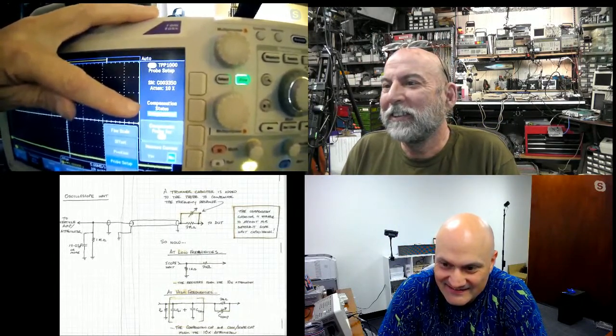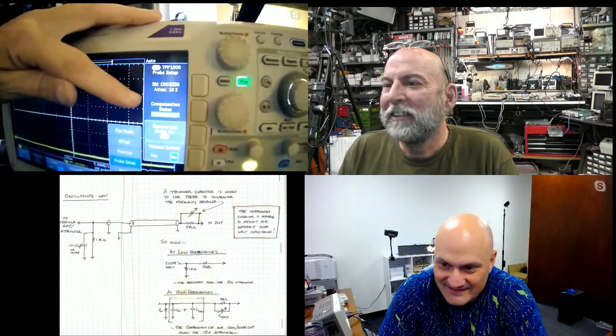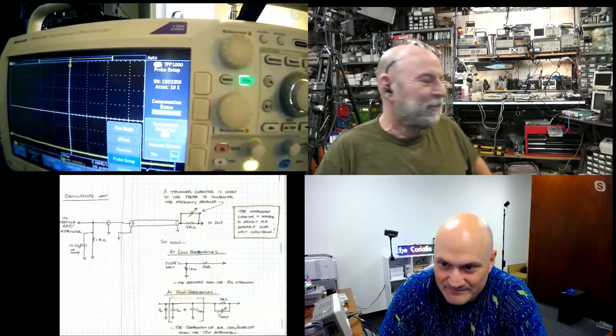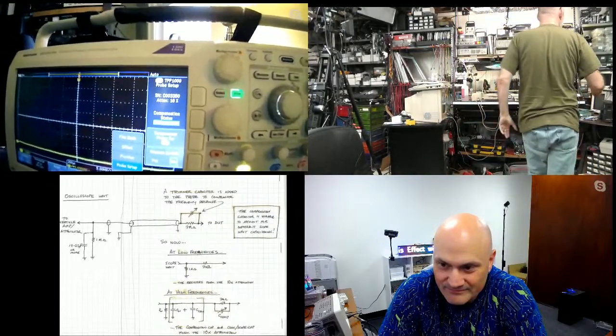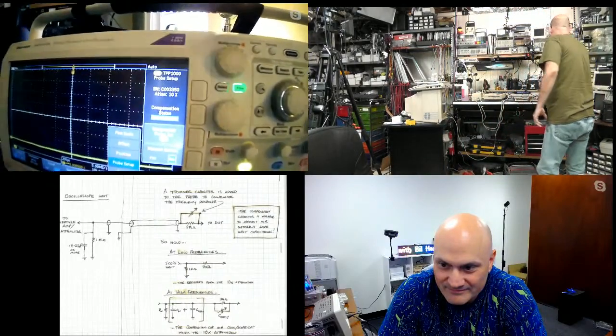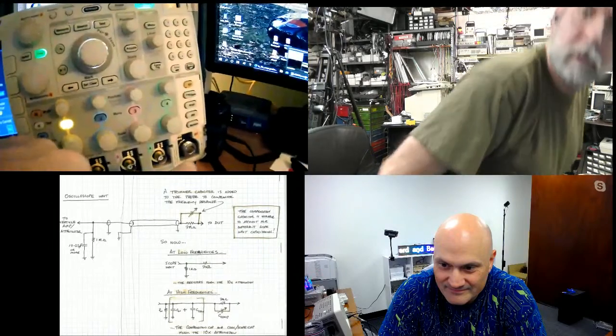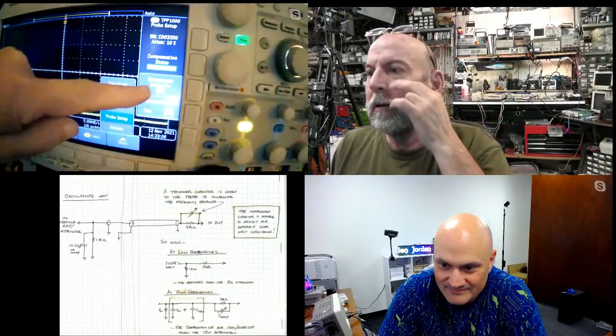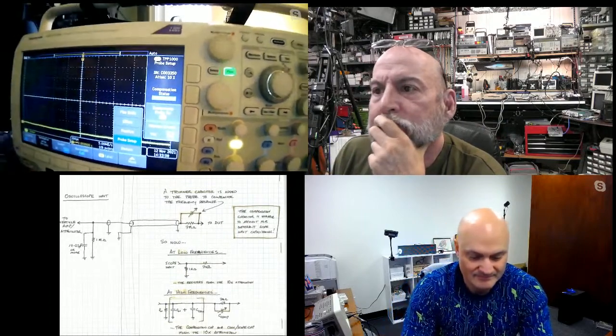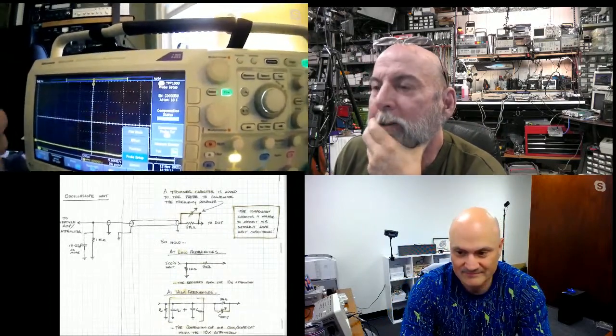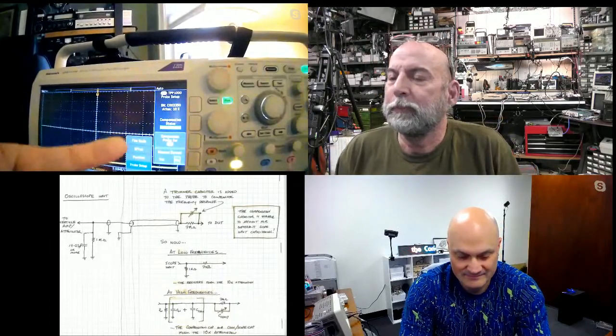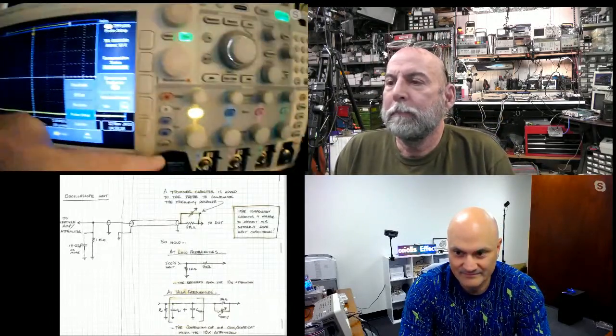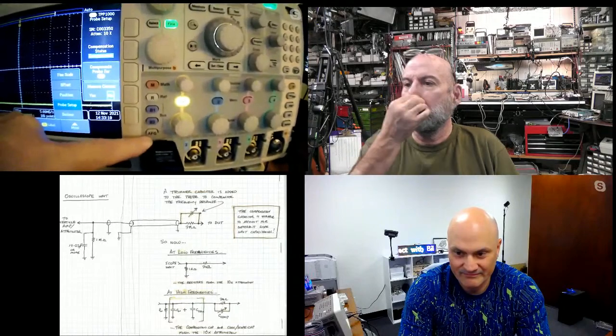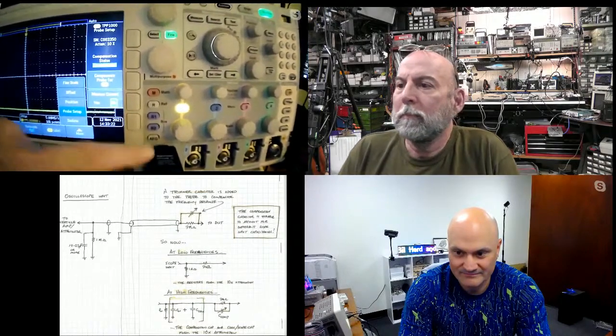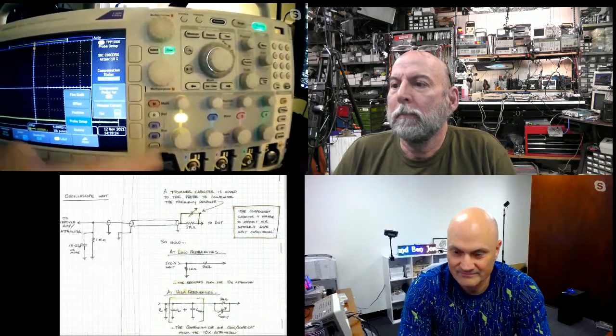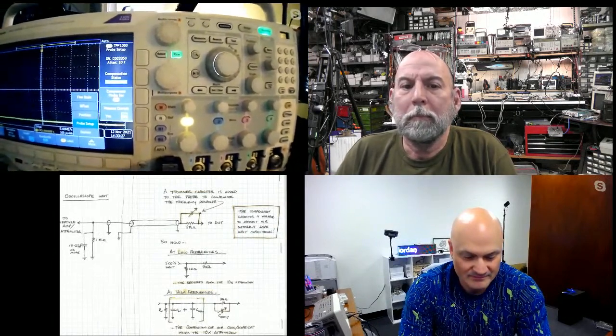I haven't touched a screwdriver on this thing, right? Well, these probes can be compensated automatically by the scope. Well, semi-automatically. What you do is you connect the probe to that compensation signal over there, and then you touch this button here that says compensate probe, and it does the adjustment for you. What it does is take the coefficients for the filter to compensate that probe and store them in a memory right behind the channel of the scope. So every time you plug that probe in from that point forward, it says, oh, that's this probe, I know how to compensate that, and it applies those corrections to it.